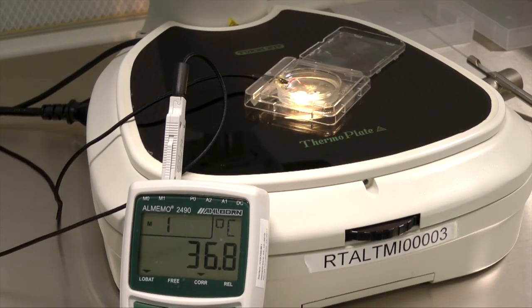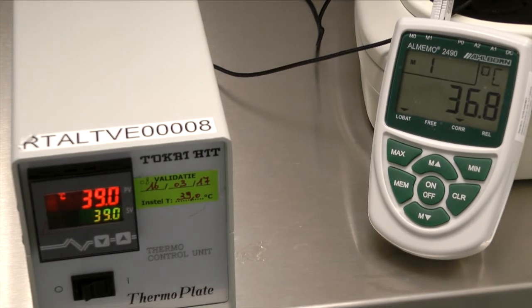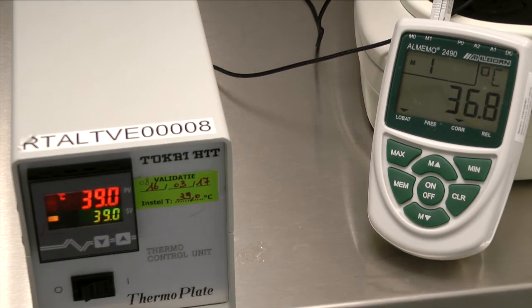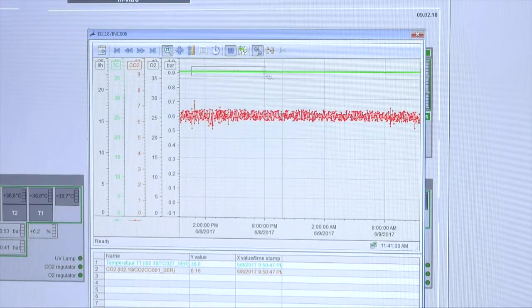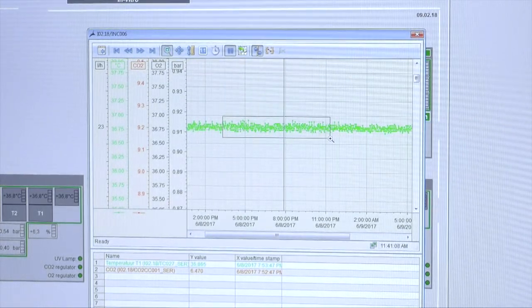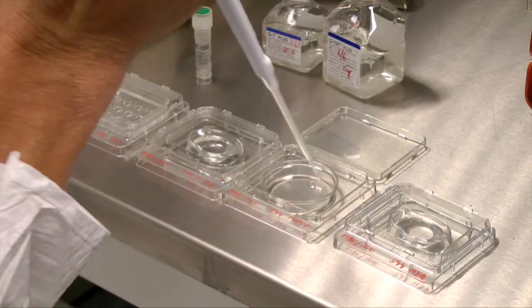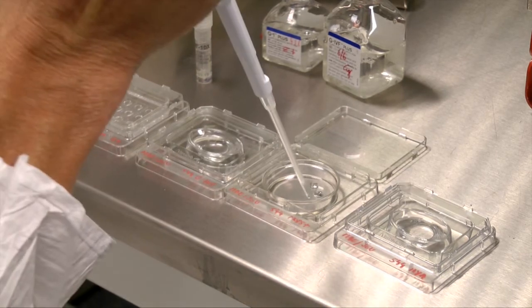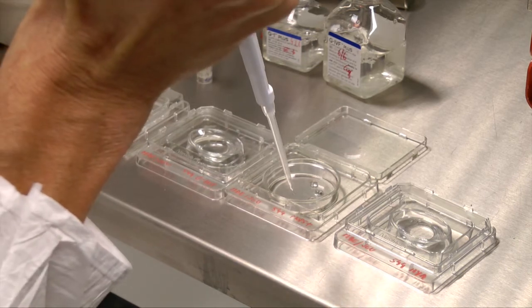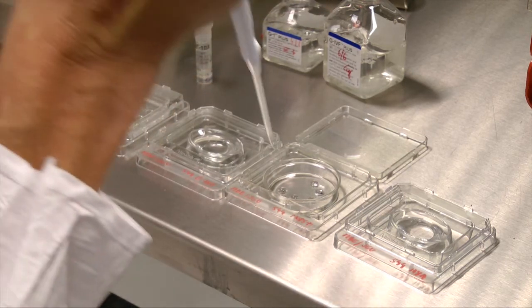This improved our way of temperature calibration and also temperature distribution in the dish. Maintaining the correct temperature is a critical environmental factor for gametes and embryos and needs to be carefully monitored. You must be aware of confounders such as hot and cold spots on warming plates, air flow in laminar hood or ventilation, and open or closed lids to ensure a safe working temperature. Because of the uniform flat bottom of the Vitrolife dishes, the temperature is the same between a center well and a culture dish, while there can be up to 0.8 degrees Celsius difference between dishes from other companies.